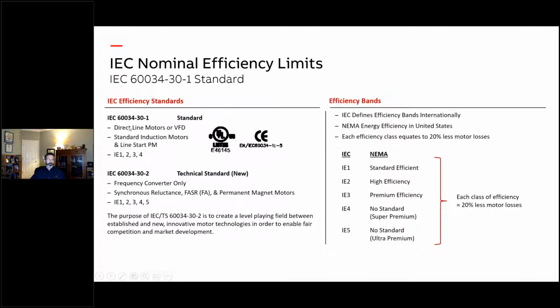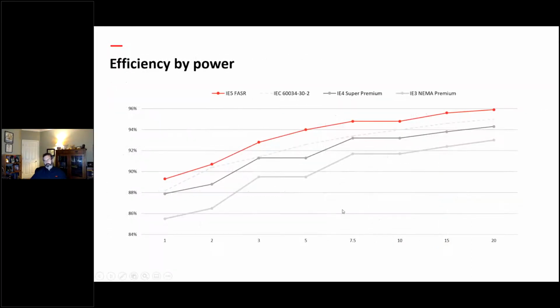There are 2 standards within the IEC world. One defines efficiency classes for direct across the line motors, which is 60034-30-1. And there's a new technical standard for synchronous reluctance motors, the ferrite assisted motors, and permanent magnet motors that have to run on a drive, and that's the -2. It's to create a more level playing field, because the newer motor technologies at higher efficiency require a drive. You can't really compare them to direct across the line motors, but we're going to do it anyway. So here are your efficiencies.